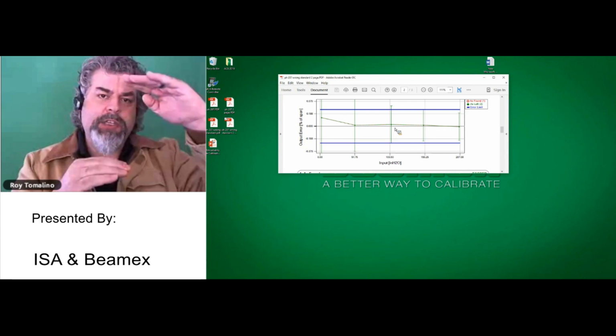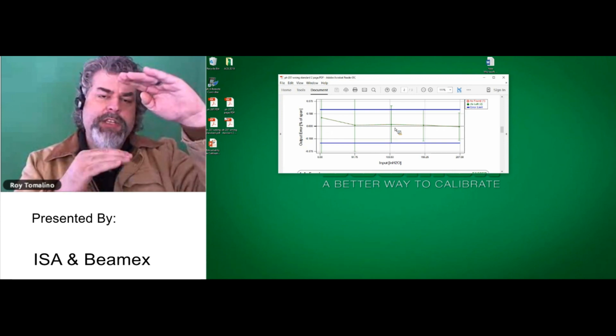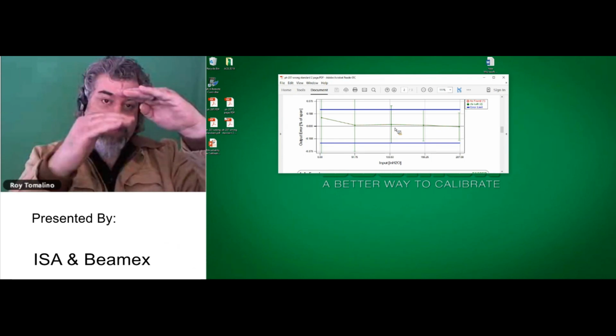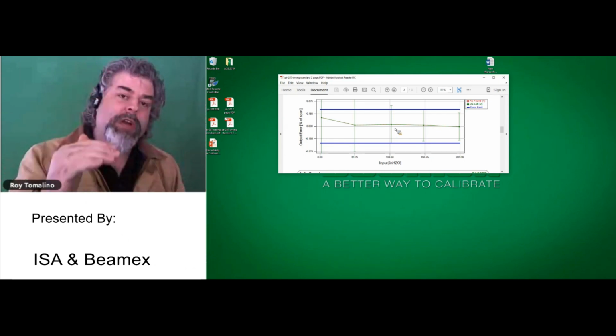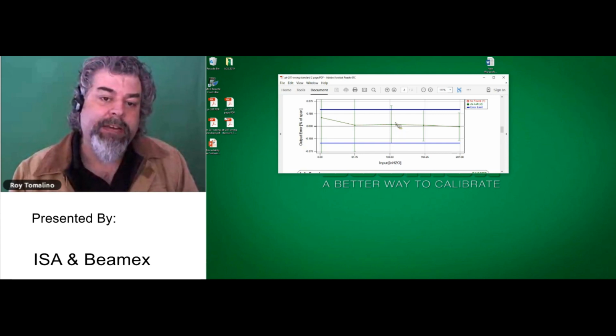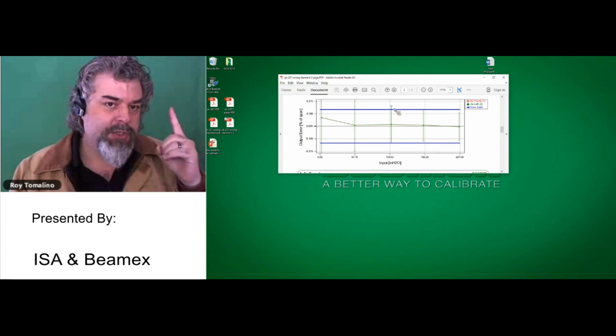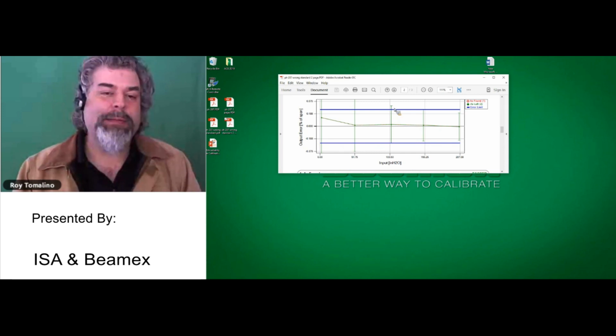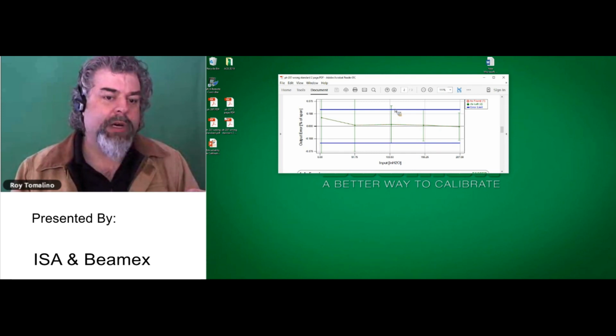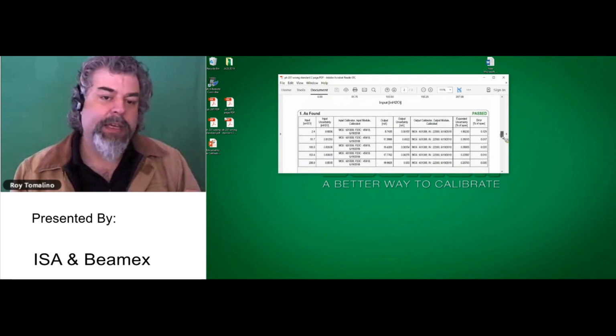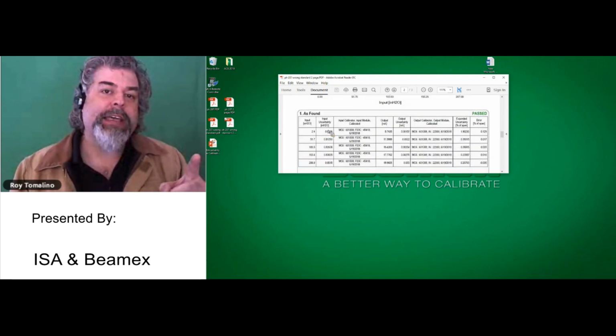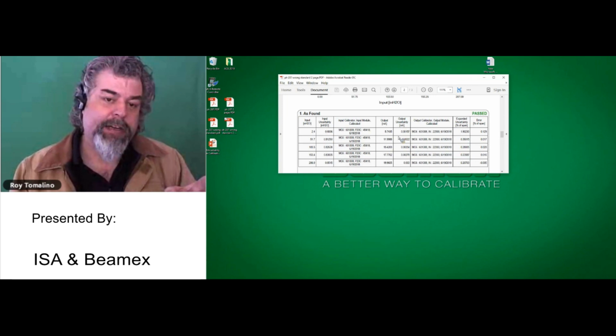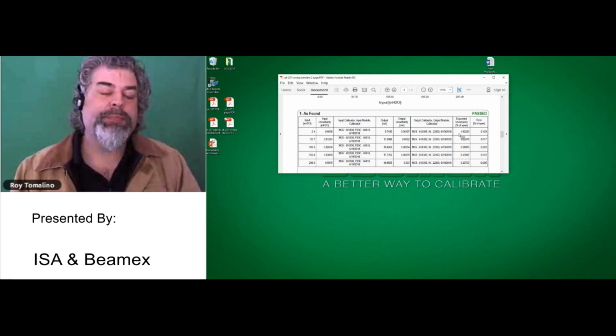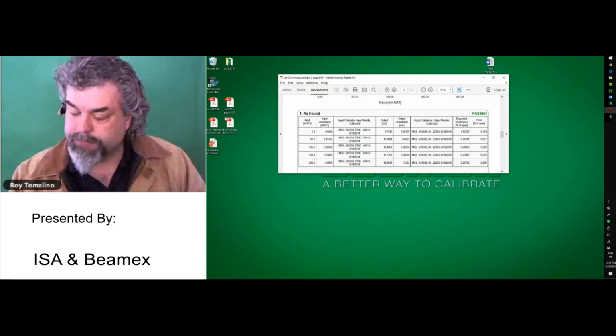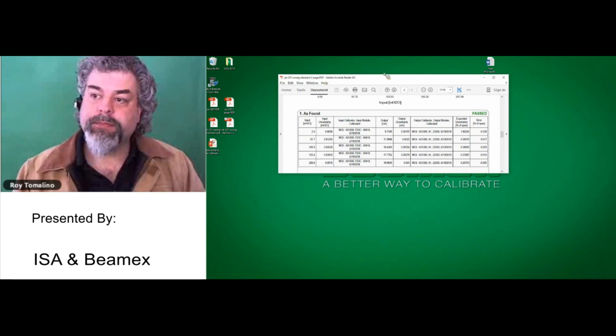You can see what we call guard bands above and below the test point. And that means that with that uncertainty, our test point could literally be anywhere along there. So this could actually be a failing test point if it's all the way up here. And this is the whole point with calibration uncertainty. I'm going to come back and do another demo that'll show you a good example. One final thing is, if I scroll down, I get an uncertainty for my input, I get an uncertainty value for my output, and then an expanded uncertainty of the two together. So with this, let's take it to the next one. I'm going to stop sharing, Mike.